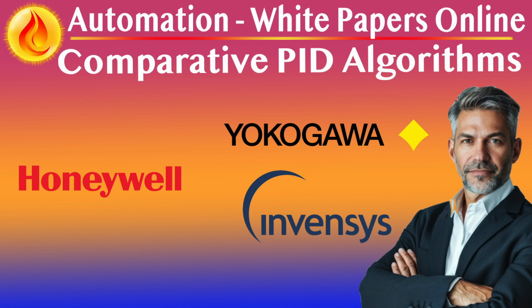For legacy migrations, Foxboro's retention of the series algorithm may reduce retuning efforts. Honeywell, however, supports TDC migration paths with embedded tools for mapping old loop behavior into Experion logic. Where derivative action or setpoint ramping is common, e.g., furnace loops, polymer reactors, Honeywell's Type-C PID and filtering logic provides safer default behavior.